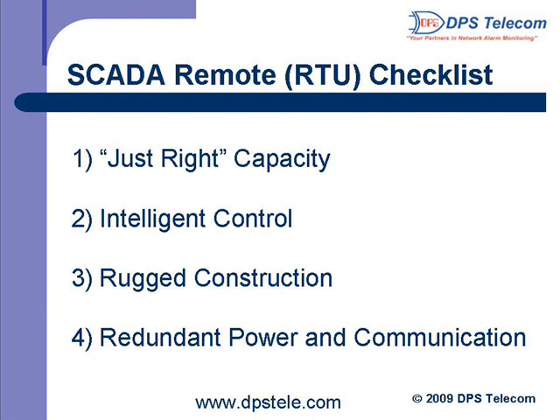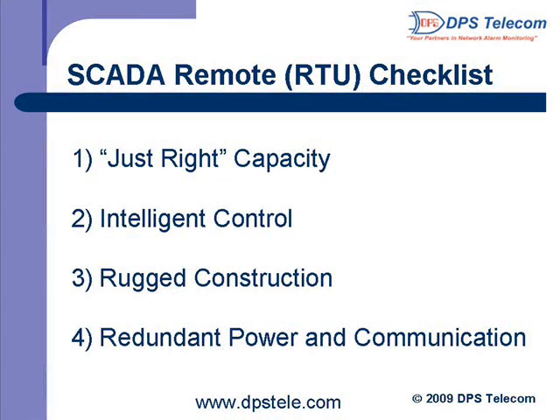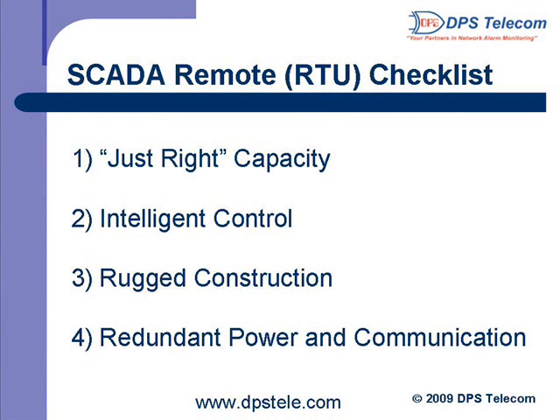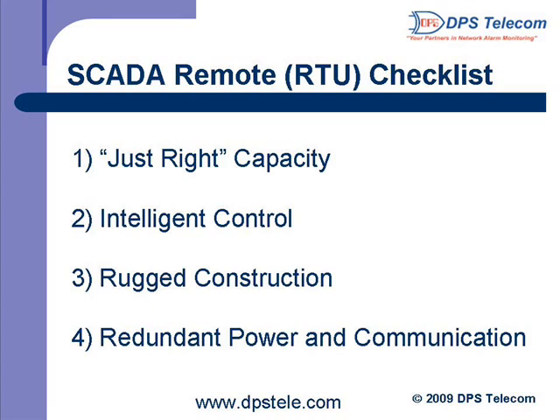Here's a checklist for evaluating SCADA remotes. Sufficient capacity: look for a remote that handles everything you plan to monitor now and leaves room for expansion, without paying for excess capacity you'll never use. Intelligent control: a remote with control relays and automation capabilities can save time by managing your SCADA system for you through programmed automatic responses. Rugged construction: a quality RTU should withstand extreme temperatures — look for a metal chassis and an industrial temperature rating. Redundancy in power and communications: look for dual power inputs or battery backup, and redundant communication paths so sensor data can be reported even if your primary transport goes down.